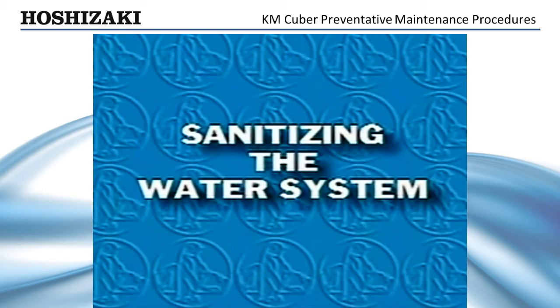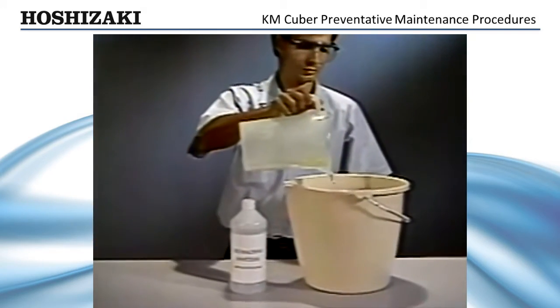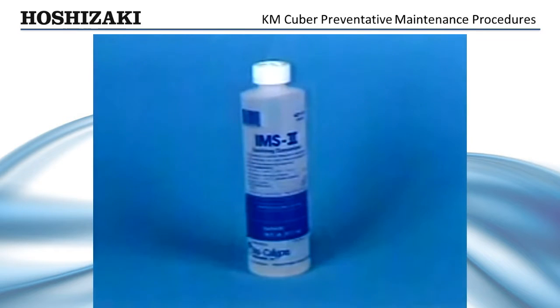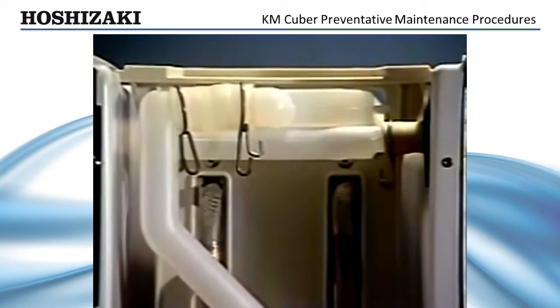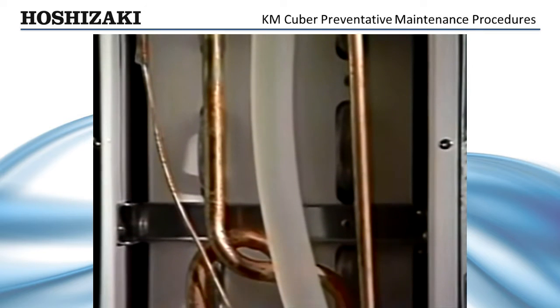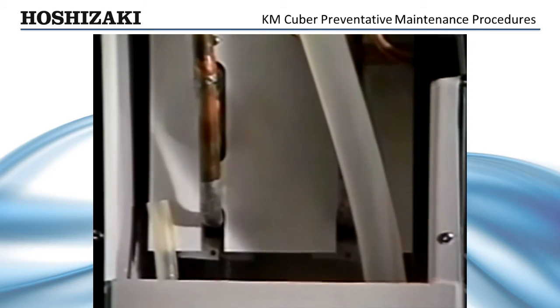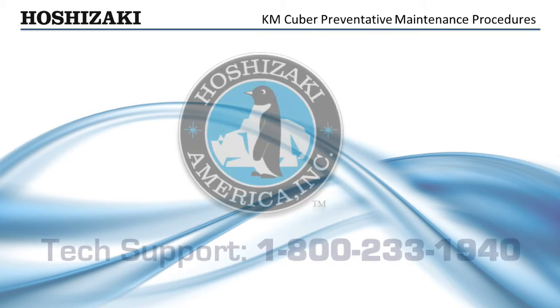This same procedure should be used to sanitize the water system. Mix a commercial ice machine sanitizer as per directions on the label, or a five and a quarter percent sodium hypochlorite solution. Circulate this solution for five to ten minutes over the evaporator surface and ribs. Flush the solution from the machine with clean, fresh water before restarting the ice maker.